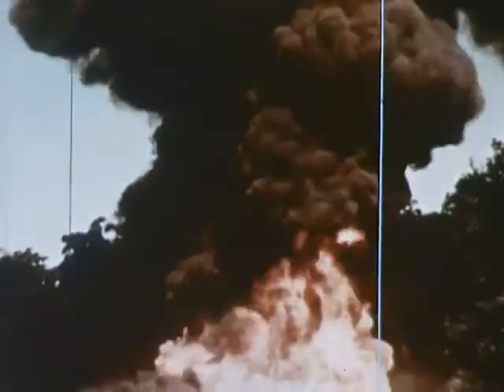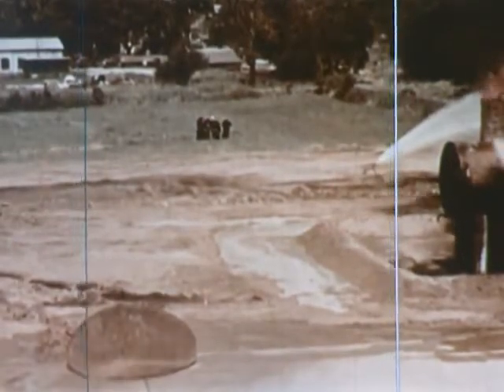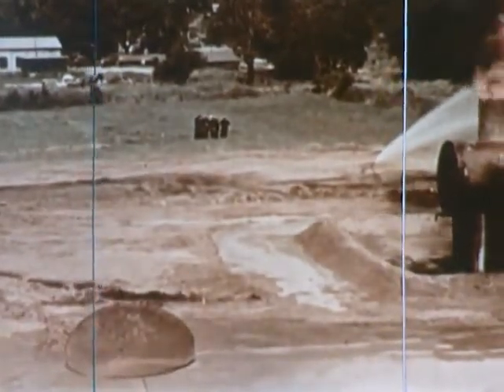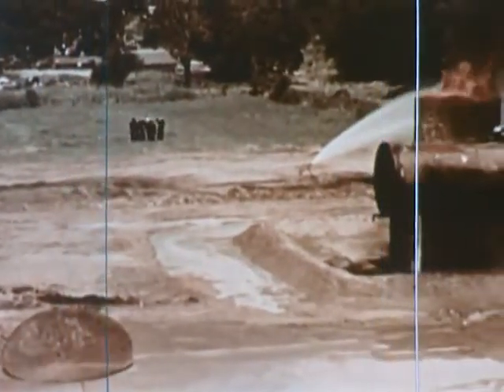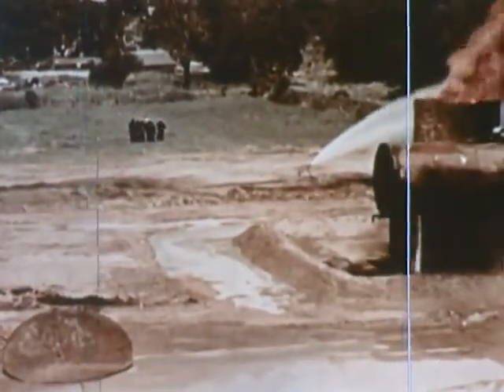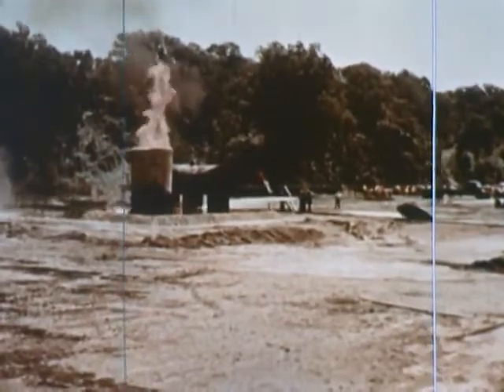Flammable liquid fires are spectacular, but even a basement fire might be more dangerous to you as a firefighter. Except for the roof being gone from the vertical tank, both tanks are intact. A hose stream was used to cool the horizontal tank, and the vent fire went out. The fire in the vertical tank was subsequently extinguished by using an aerial ladder pipe with a 500 gallon per minute fog tip set in a narrow pattern.